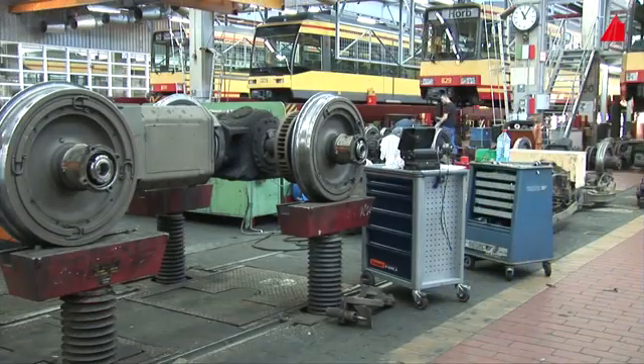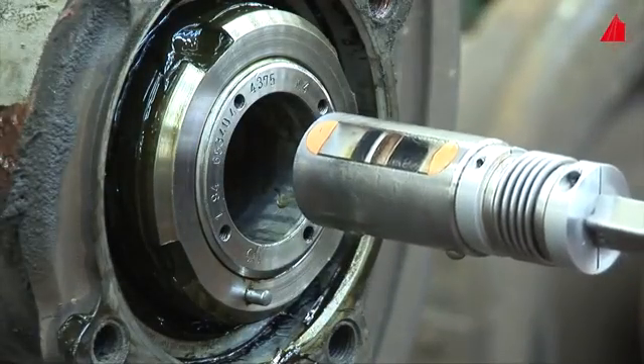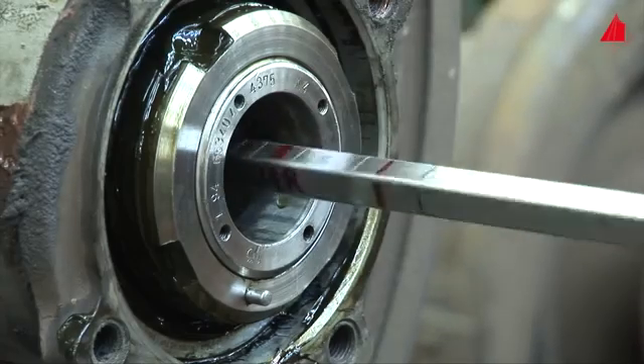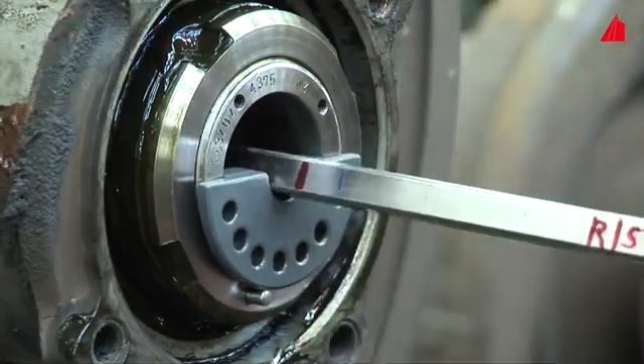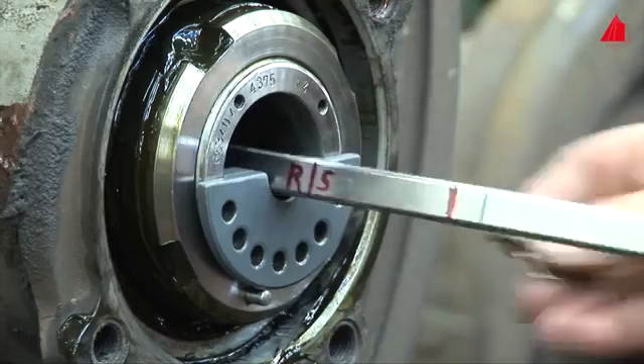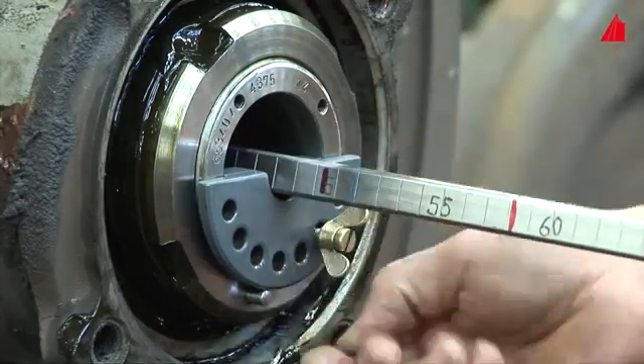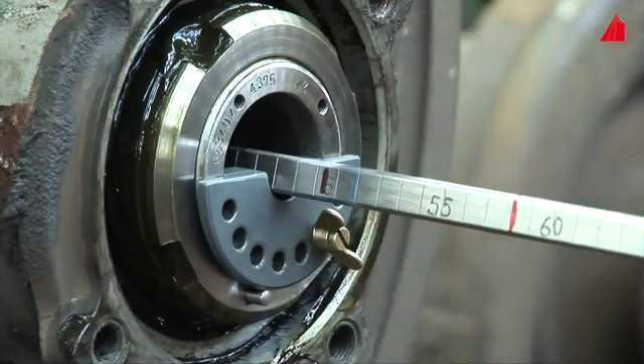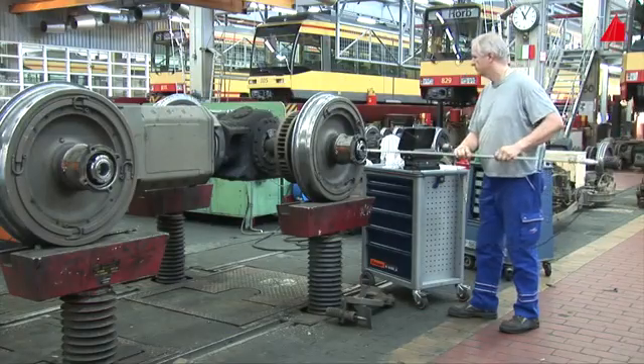Now he takes a special probe designed exactly for this purpose, inserts it carefully into the bore with the mount, and evenly spreads out the couplant by turning and pushing. He has accurately marked the most important examination points at the mount. In an experienced manner, he positions the probe at the appropriate places within the wheel set axle and watches the monitor closely.